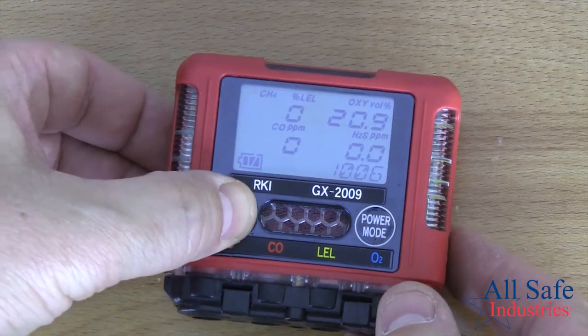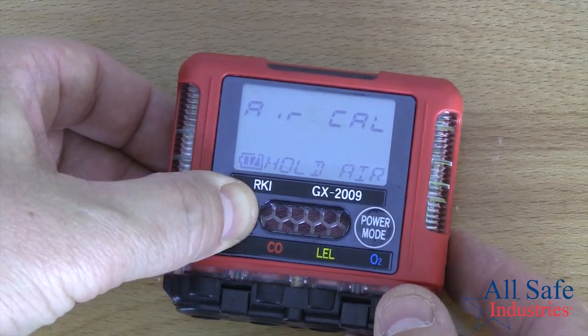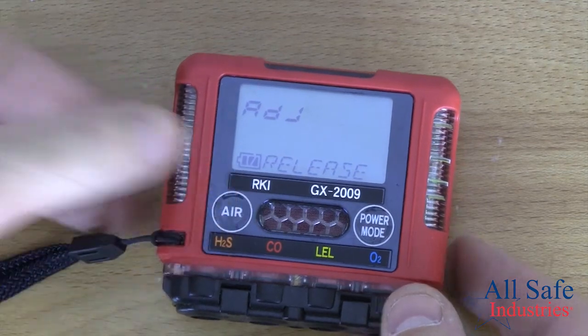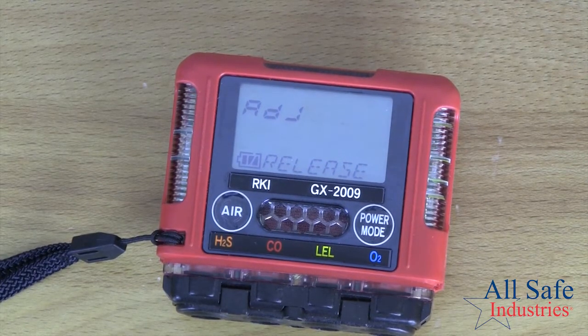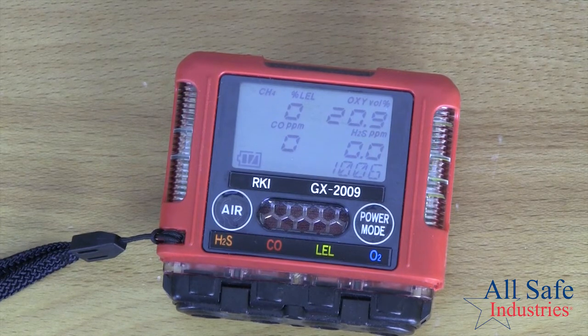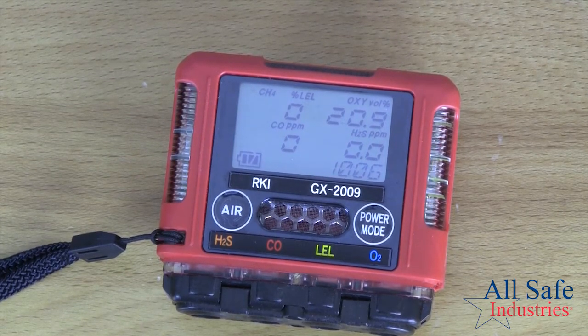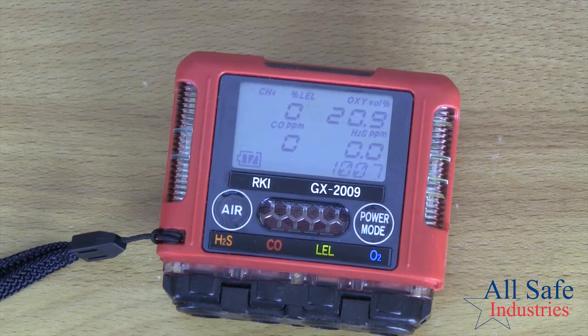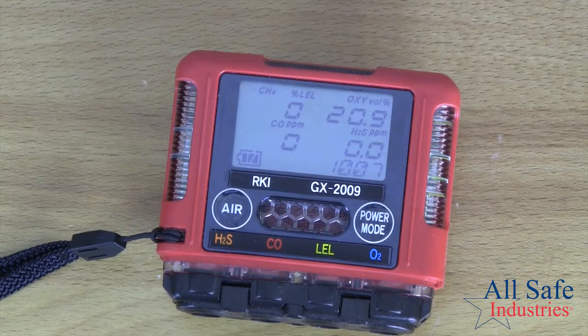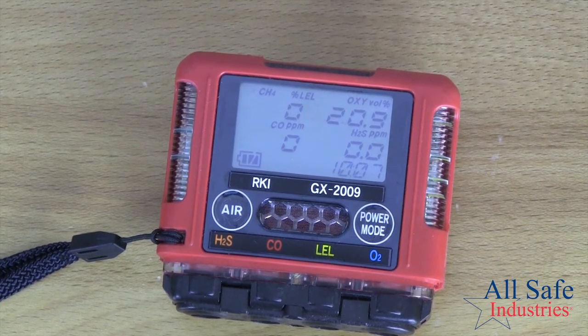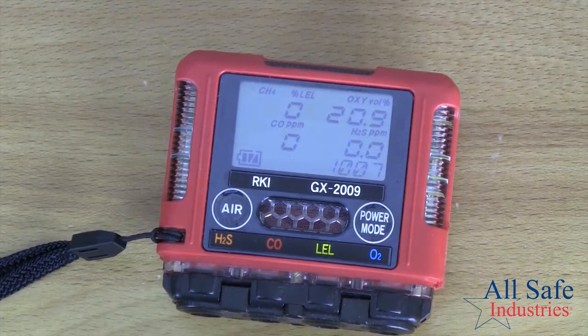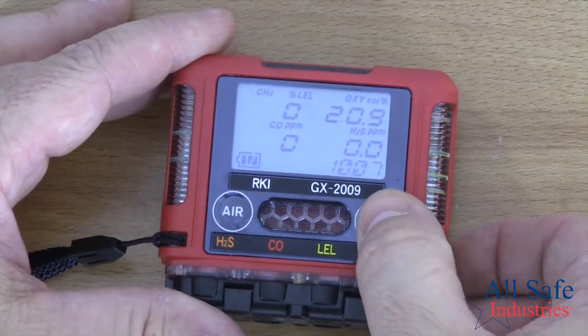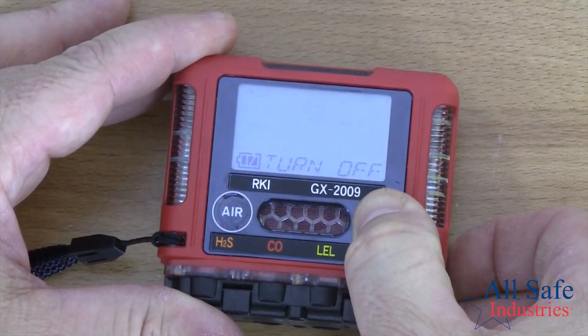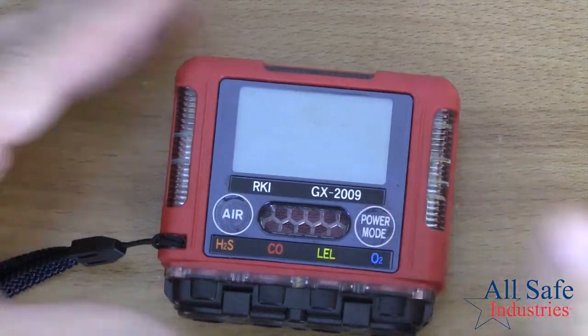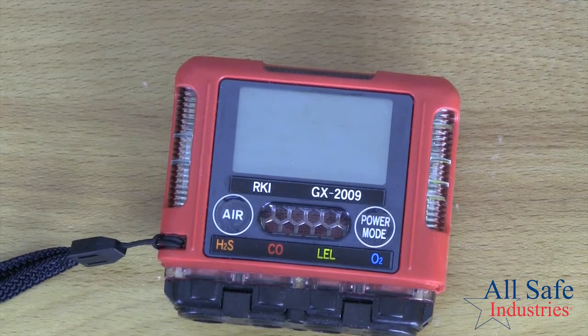If we press the air button, this is how we activate a fresh air calibration. So you'll see it says hold air, and then it tells me to release the button. And that's how it's going to jump in and do a fresh air calibration. And then it shows us that all the sensors have been reset to 0, except for oxygen, which is reset to 20.9%. And it's like hitting a big reset button. Just make sure you're in fresh air when you do a fresh air calibration. So really the last thing we can do in regular run mode is to turn off the meter. You just push and hold the button, it will beep 3 times, and now the meter is off. And that's as easy as it is to operate the GX-2009.